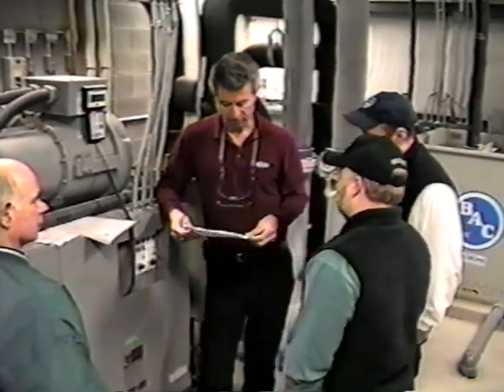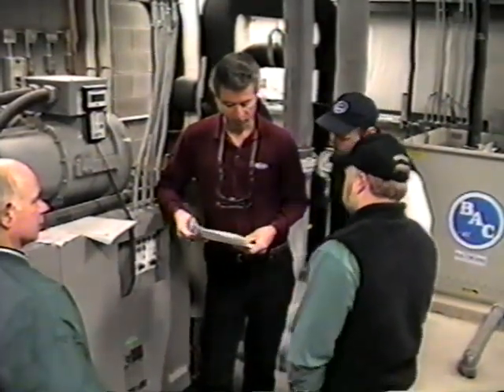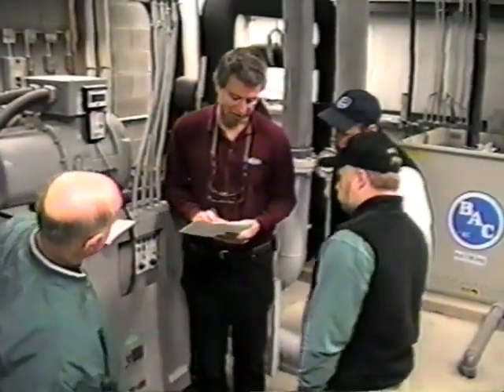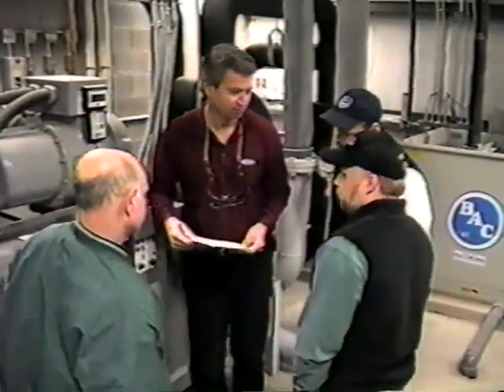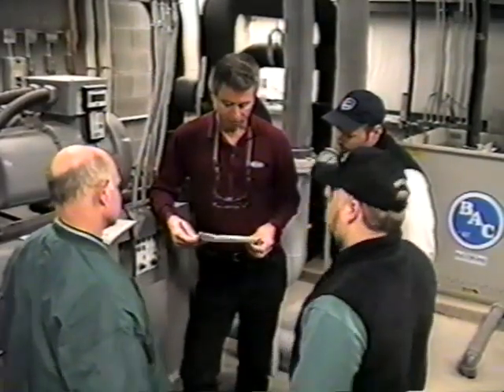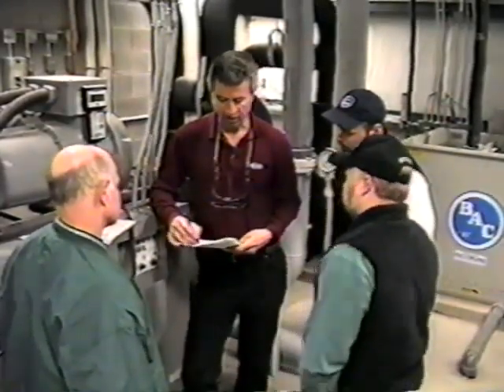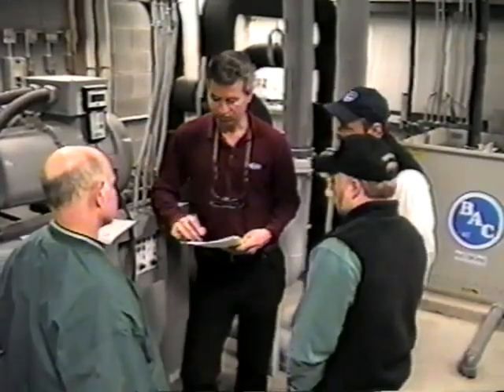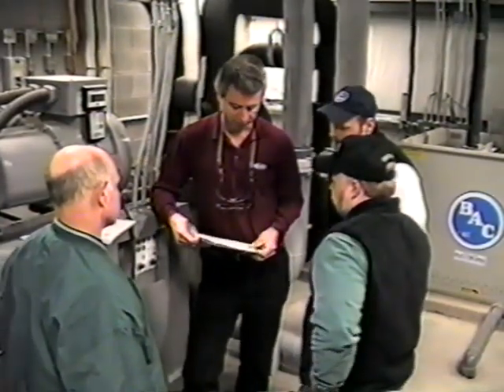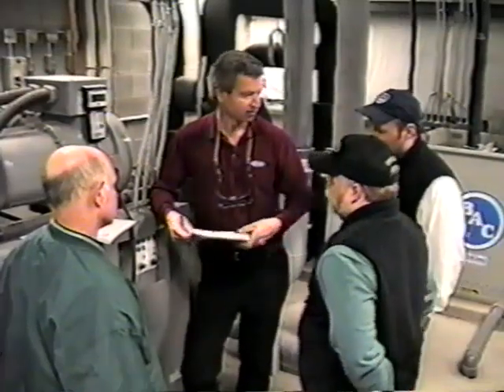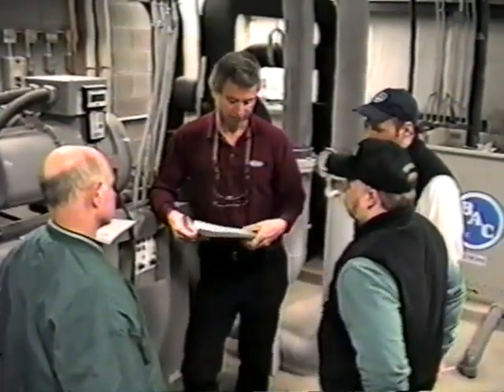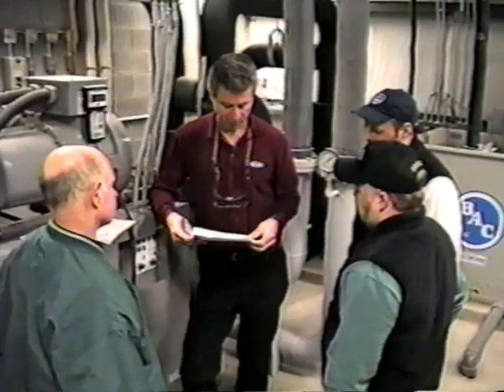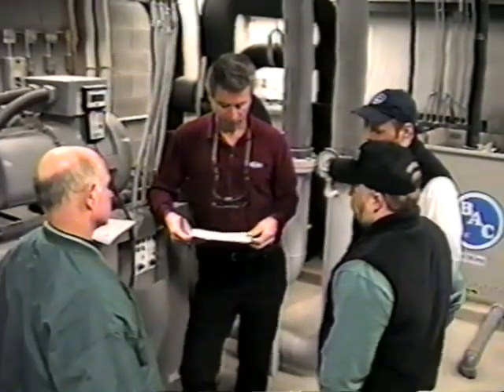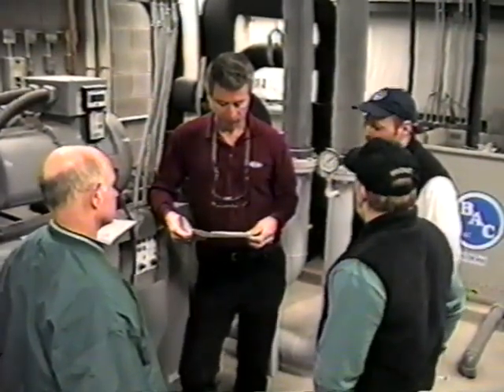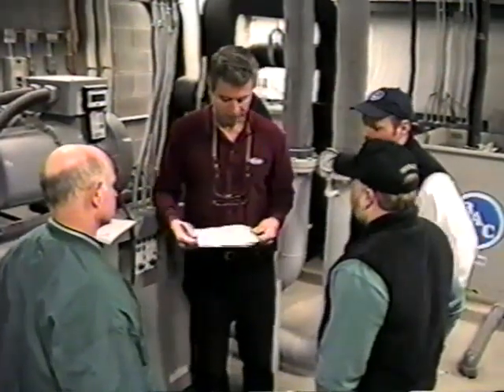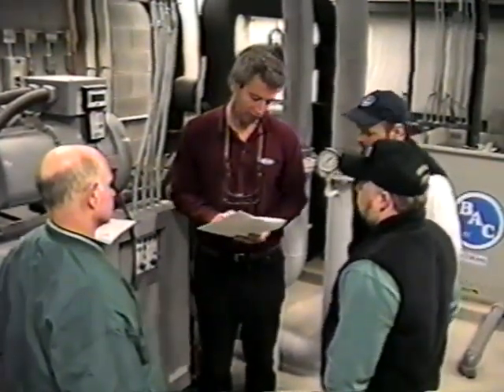These aren't that critical to take. You could take compressor A1 running. Like I say, any place where you see an A2 and a B2, you don't have those anyway, so there's not going to be a reading there. Or what you might do is go through and put an X on the lines for the ones you don't really want, and still use this, so at least you can utilize the functionality of placing it in a certain mode. Right. The ones I didn't use, I can recopy it in that sequence. Yeah, this wouldn't be bad to take.